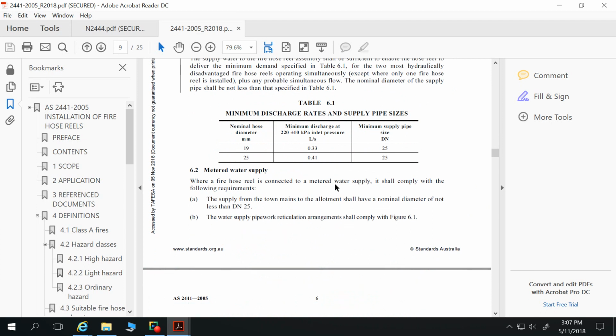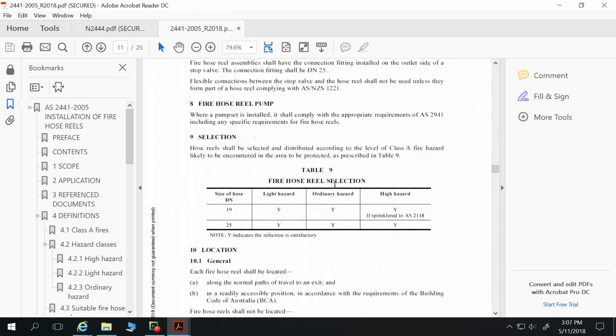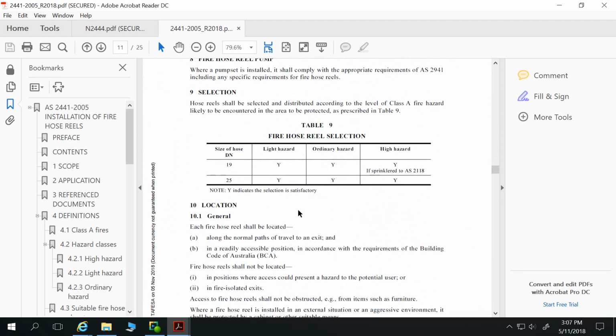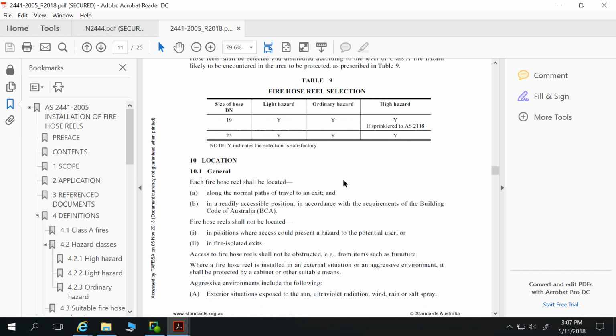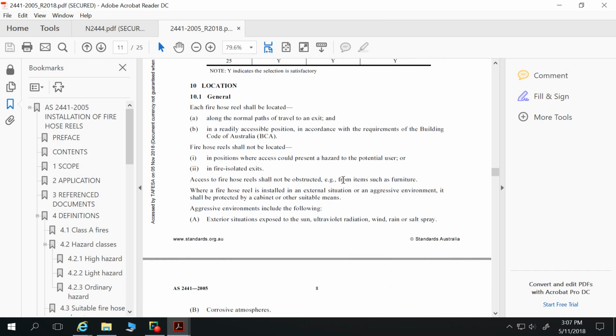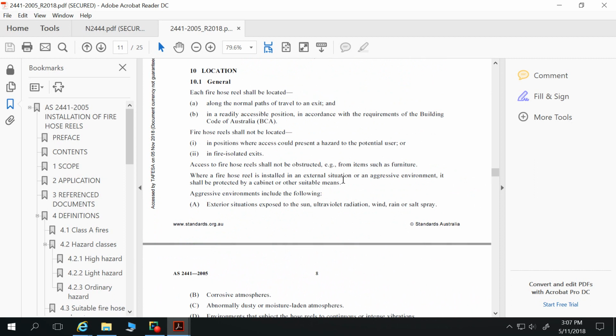So that's about pressure supply. So we're looking at a mix of light hazard and ordinary hazard. I think we can be fairly confident about our 19mm hose. So in terms of deciding where to put those fire hose reels, each fire hose reel shall be located along the normal paths of travel to an exit and in a readily accessible position in accordance with the requirements of the BCA, or now the NCC. Fire hose reels shall not be located in positions where access could present a hazard to the potential user, or in fire isolated exits.